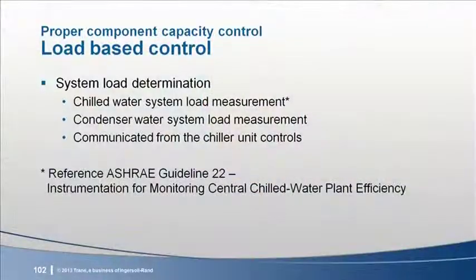There is one more question that needs to be answered. How would the control system go about determining the system load that will be used for the basis of this control? There are several ways that can be implemented effectively. The ones shown here are the most generic. We've referenced ASHRAE Guideline 22 because it contains an excellent set of requirements and recommendations for measuring chiller plant capacity and efficiency. If the instruments required for accurate load determination are not designed into the plant, it can be very difficult to add them after the fact. There are other acceptable methods of capacity determination that can be implemented, some of which might be proprietary to one system or chiller type. You could even implement multiple methods and use them as validations of each other. The main thing to note here is to choose a method that is reliable, repeatable, and sustainable.